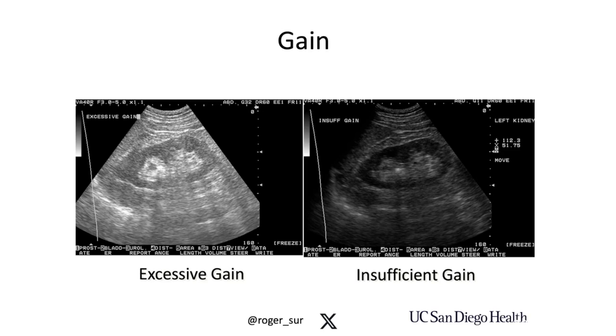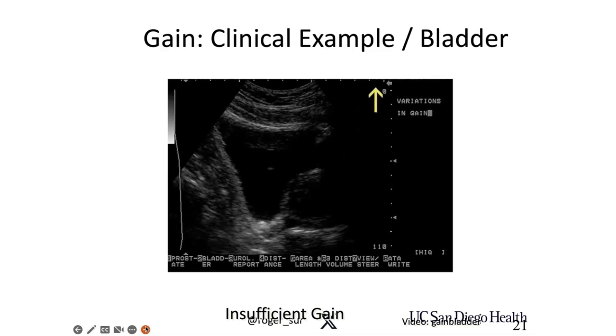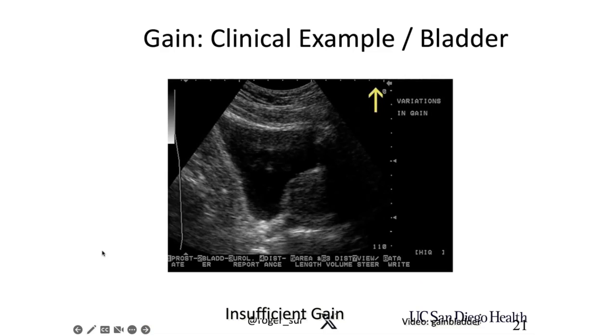Now, on the left-hand side, the sensitivity of your probe is very high—the person has turned up the gain, so there's too much gain, and it's too bright. On the right-hand side, the gain is insufficient—not enough gain. So it's a matter of turning that dial to optimize your gain.